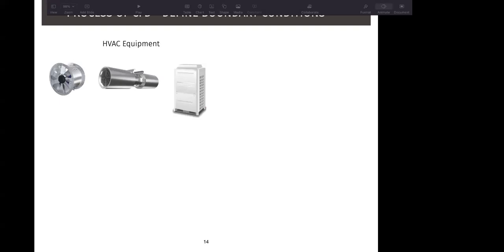So now the next part of the process is to apply boundary conditions. And what we mean by boundary conditions is the initial condition to the problem. So in this case, if there are any jet fans or exhaust fans being applied to the problem, that would be the boundary condition. For a thermal comfort study, if we are looking into air conditioning and we are applying an ODU or an indoor unit, that would become the boundary condition to the problem. Now, that would mean that we would need to have the physical structure, the physical equipment, as well as the CFM, the temperature through it, the velocity through it. So these data then become the boundary conditions for that problem.